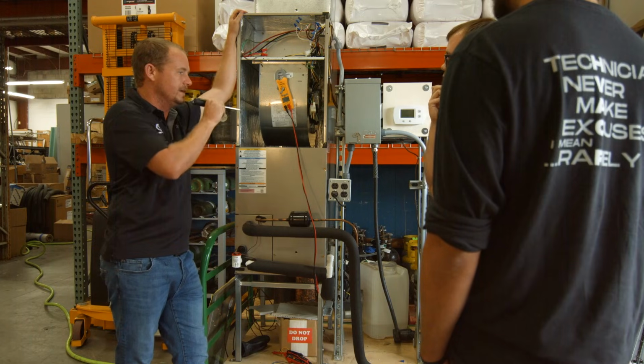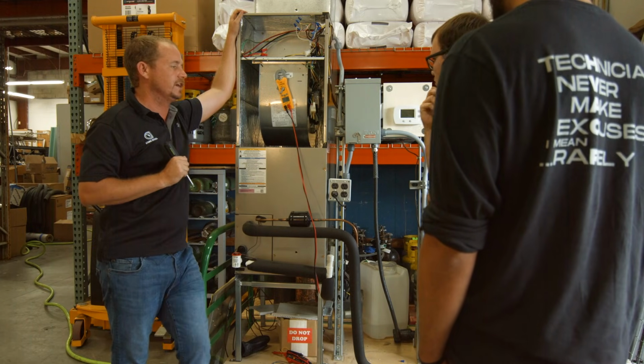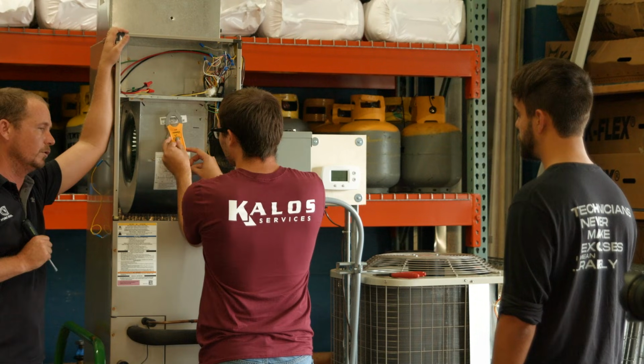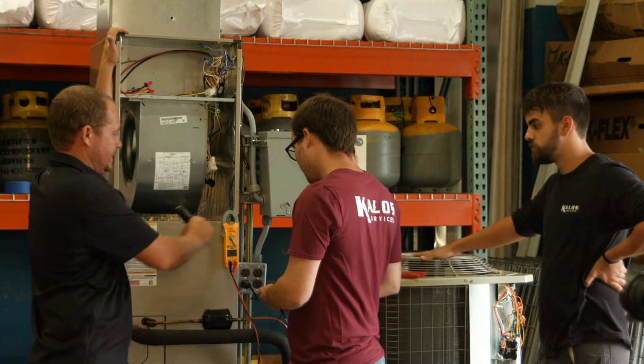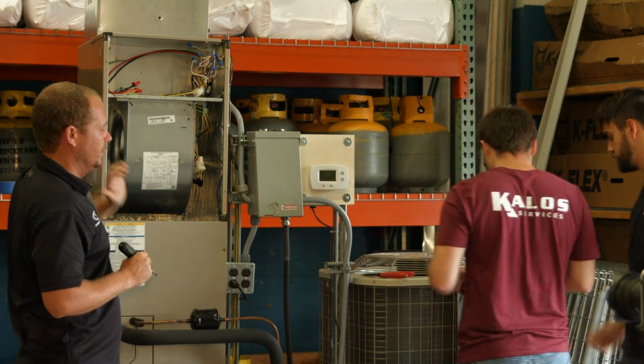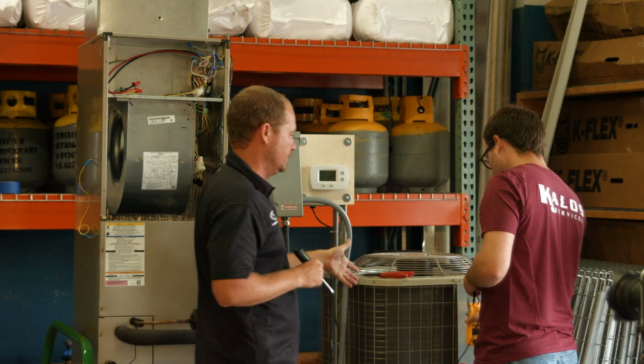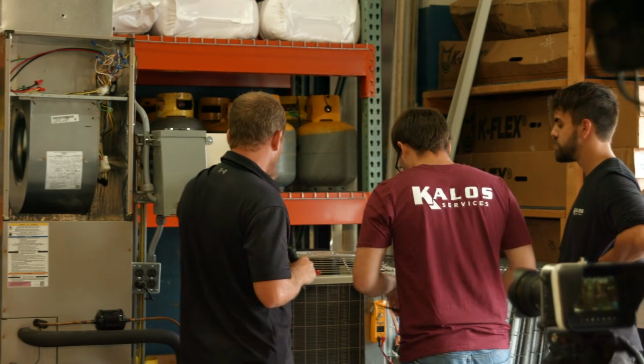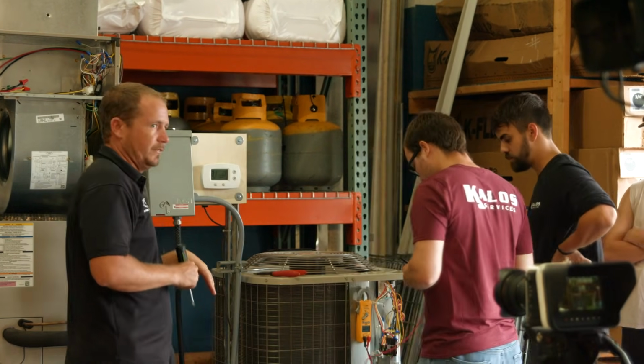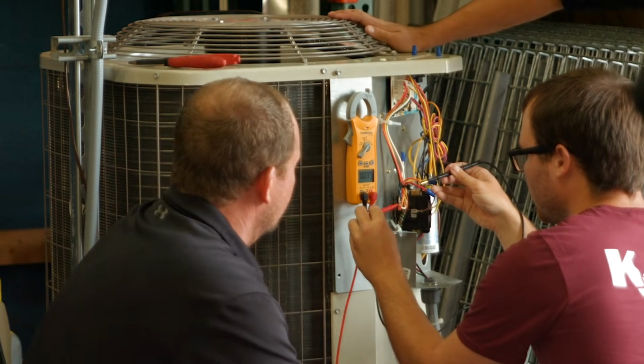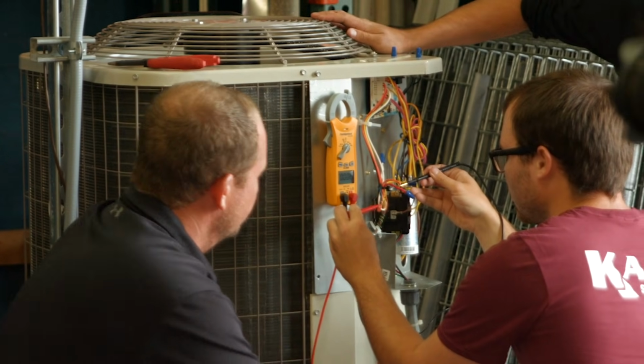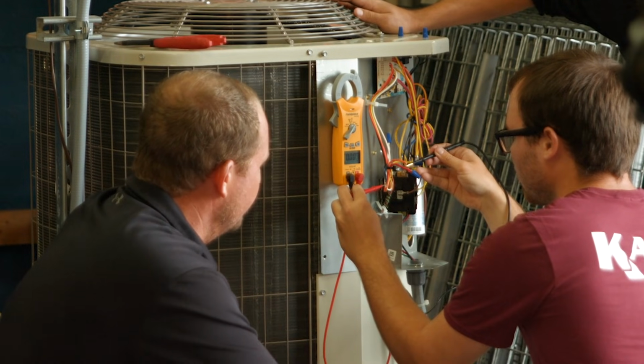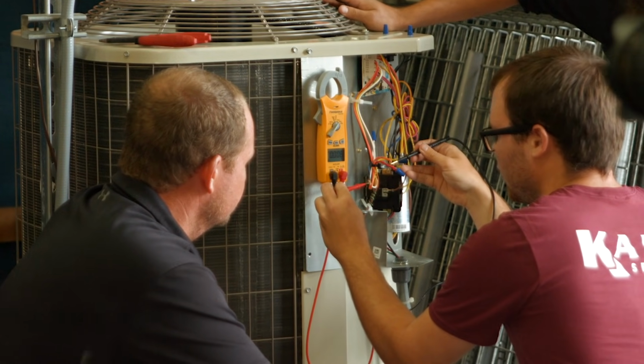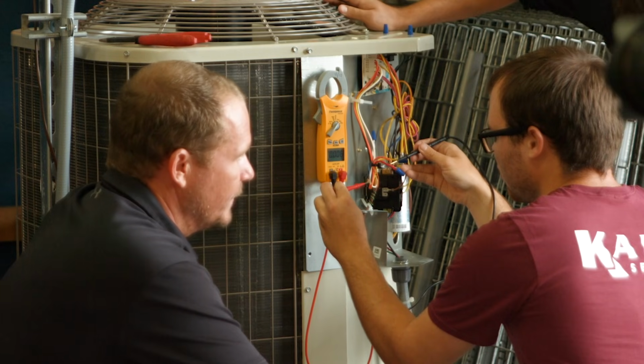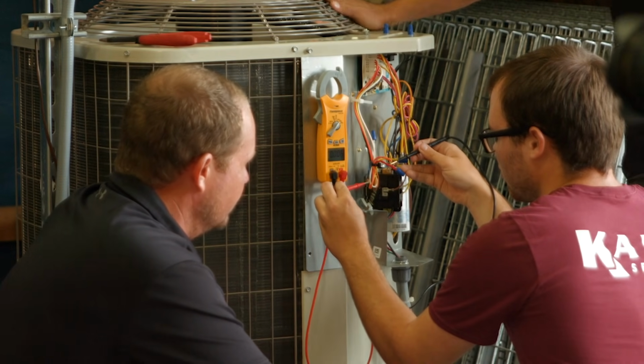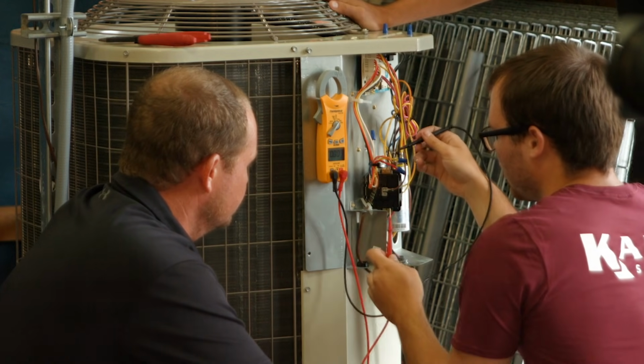All right, so let's grab your meter and let's fire it back on and check to see if we have 24 volts. I would just check it outside, like Eli said. You're not turning on the condenser because we don't need the condenser to short cycle right now. We just need to see, are we getting an O-call from the thermostat through the air handler? All right, so we're checking from orange to common, and we have a little bit of ghost volts, but nothing, nothing really, right? So that's an indication of what? This is not getting it.